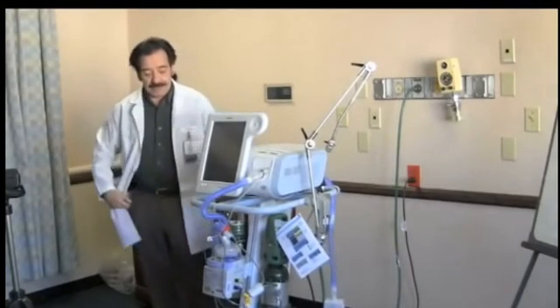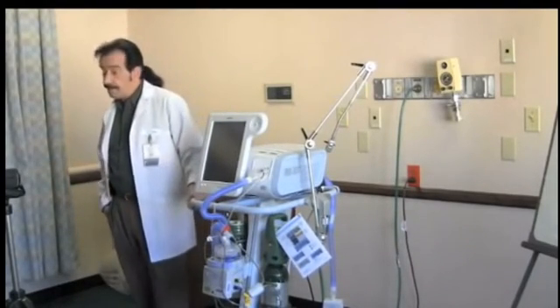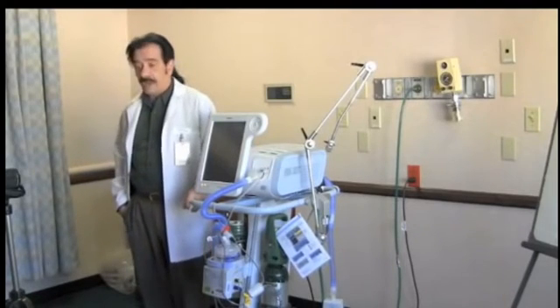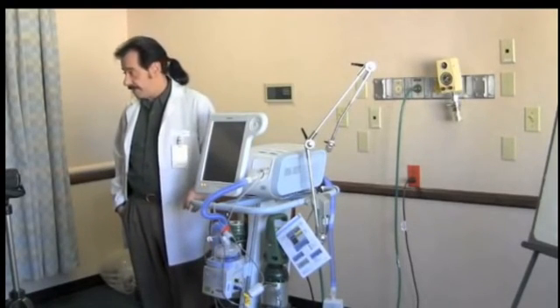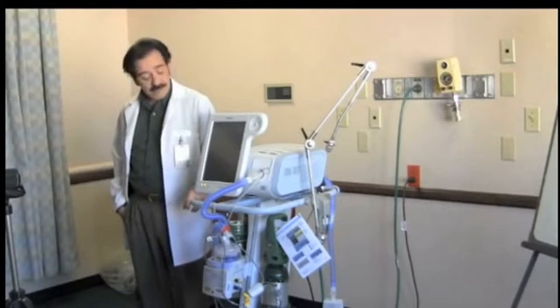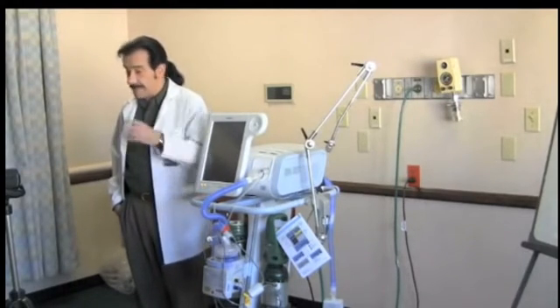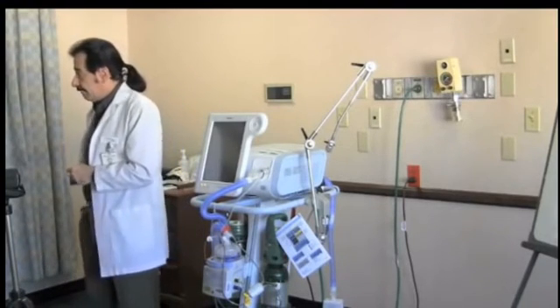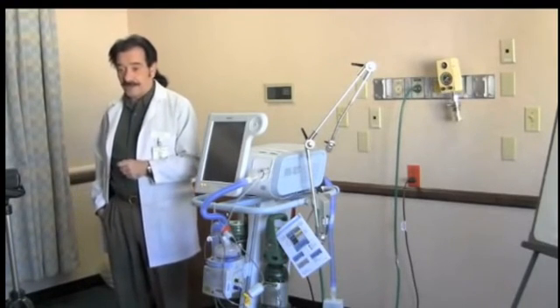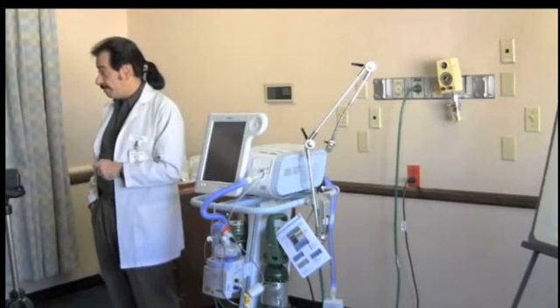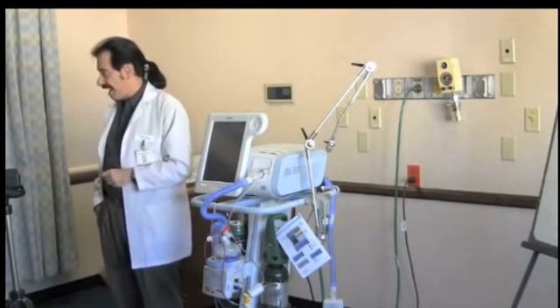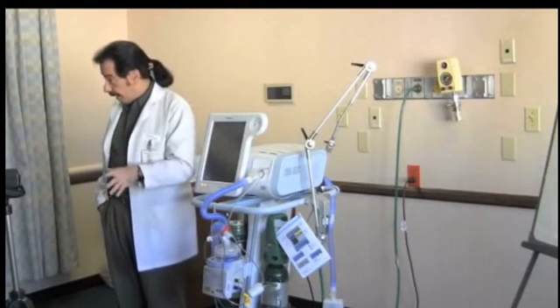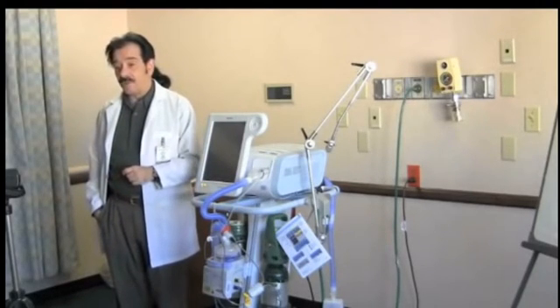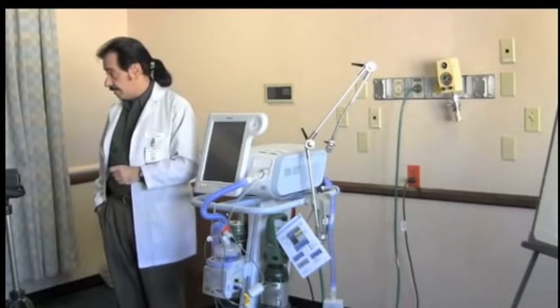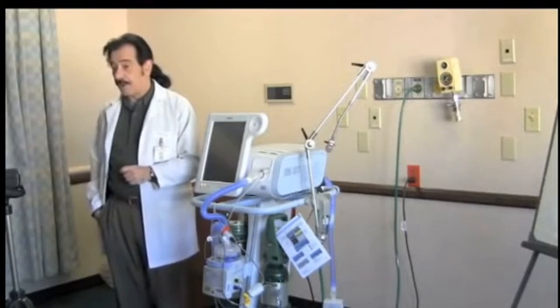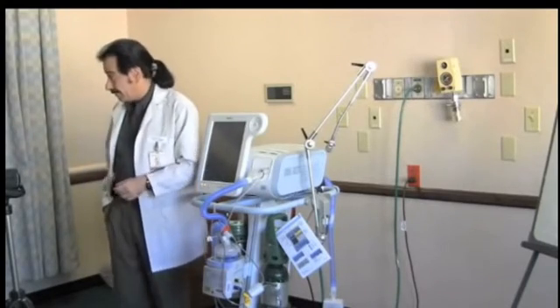So if I have a situation where the patient's drawing a volume of 500 cc's with an IPAP of 18, an EPAP of 6, a respiratory rate of 20, and a mask leak of 20 liters a minute, if the patient's being transported at 100% FiO2, the E-cylinder will last for 15 to 18 minutes. Okay, so go fast. Now, with those same parameters, but an FiO2 of 30%, the E-cylinder will last for almost 100 minutes. So a big difference there.